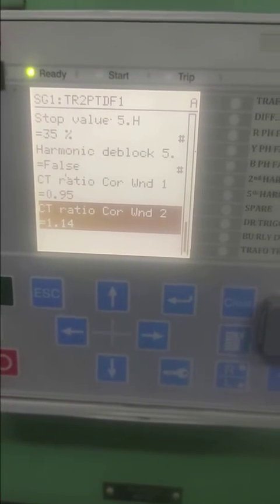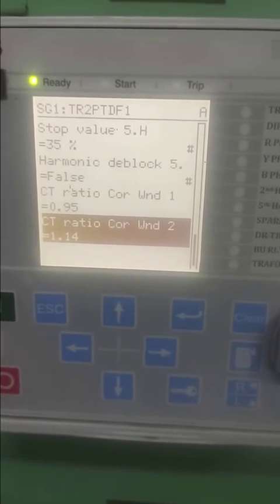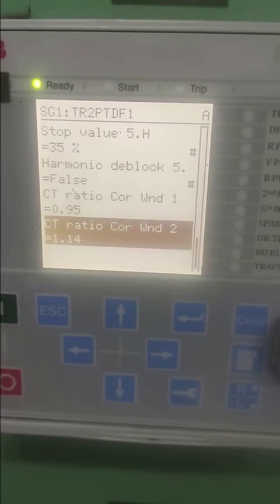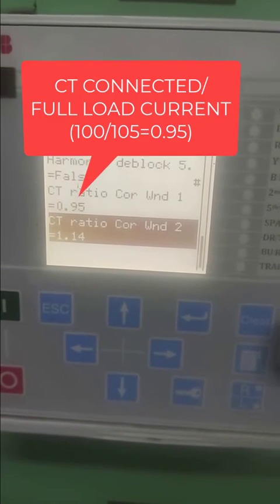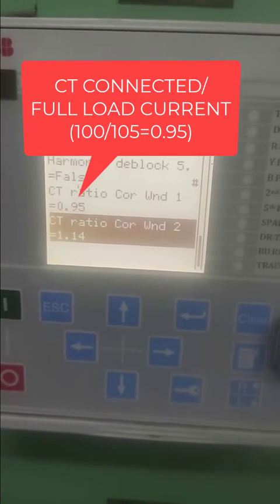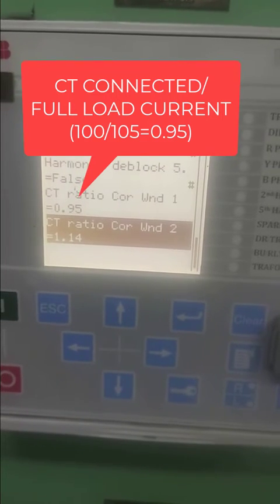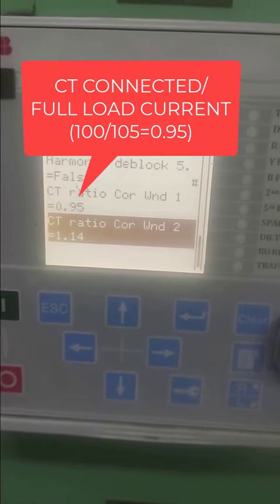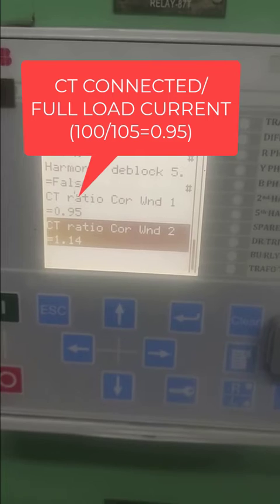Here's what I have shown: the CT ratio for HV side is 100 connected. Your full load for 20 MVA transformer is 105. Divide 100 by 105 and you will get 0.95.